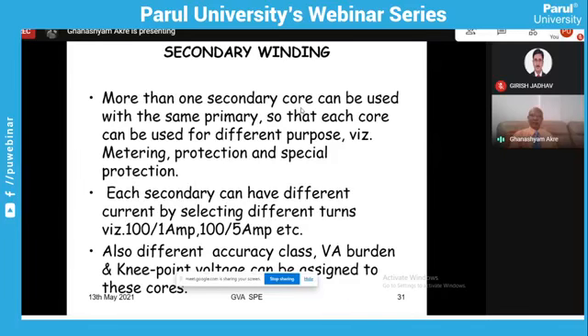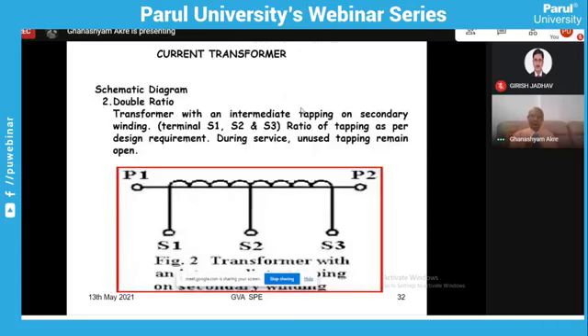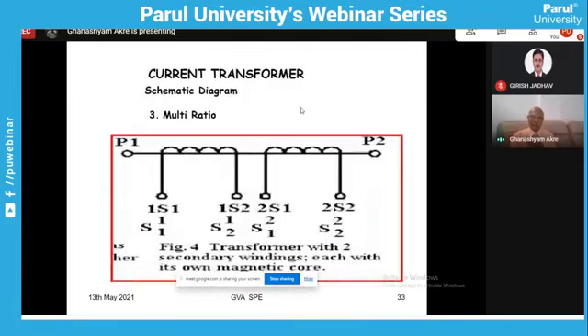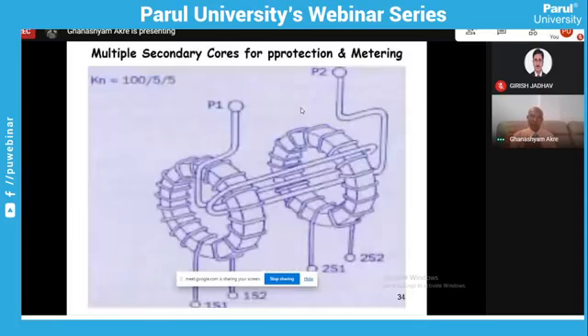Similarly, the secondary can have tappings, as I showed you earlier, that is 100 by 1 ampere will also have a tapping of 150 by 1 ampere. Similarly, here is the same common primary and a tapped secondary. These are two separate cores on the common primary. This is how it will look in a toroidal core. The primary has this loop together and the cores are different with the secondary connections different.